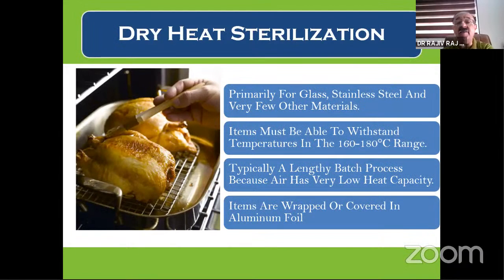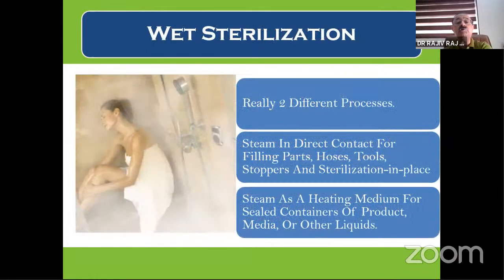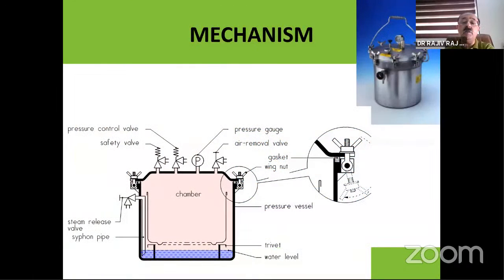Dry heat sterilization is used mainly for glass, stainless steel, and a few other materials. The temperature that the item should be able to withstand has to be higher, and you cannot wrap it in cloth. It has to be wrapped in aluminum foil. The most common method today is wet sterilization, which basically is steam that goes through the hollow parts and inside various crevices of your packing material. And when the steam is heated, the bacteria are killed. The basic principle: there's some water which is heated that goes in the form of steam, and this is controlled once the temperature of 134 degrees is achieved. About 3 to 4 minutes is more than adequate.